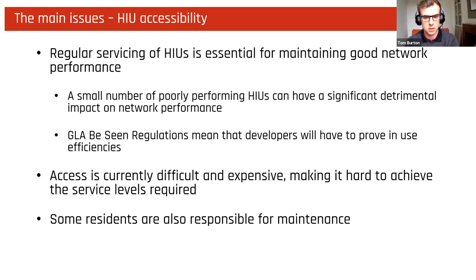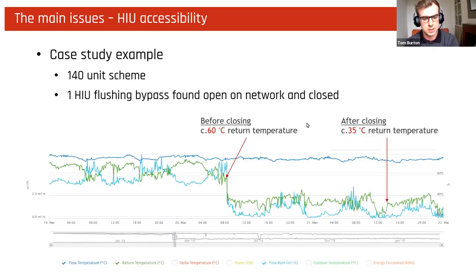To give an example of the impact that accessibility can have on a system, this is a case study of a project we worked on. It's a 140 unit scheme, and this graph is of the block level heat meters. You've got the flow temperature in dark blue, the return temperature in green, and the flow rate of the system in light blue.